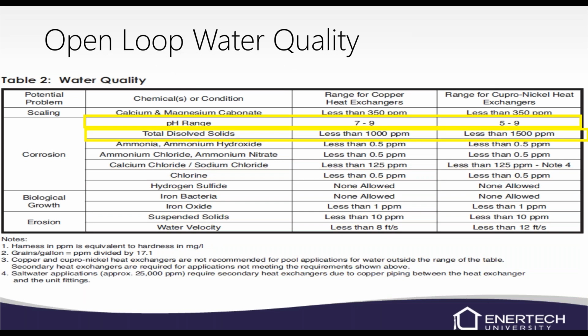Again, we talked about open loop water quality. pH is a big concern. You may want to check the dissolved solids in a well system. That's where I see it the most often. But again, ammonia is a big one. You see a lot more ammonia than we have in past years. It's just slowly getting worse and worse throughout the whole country.